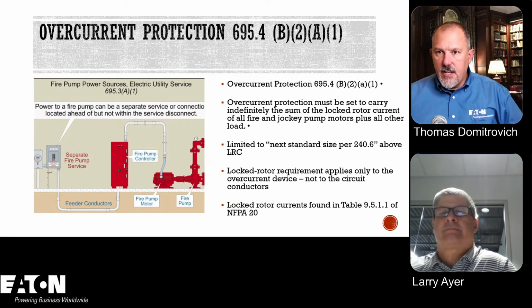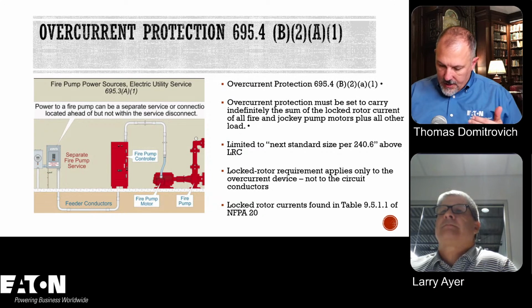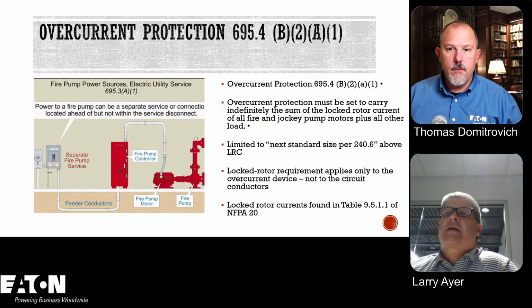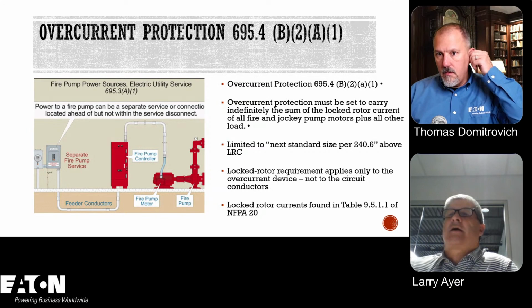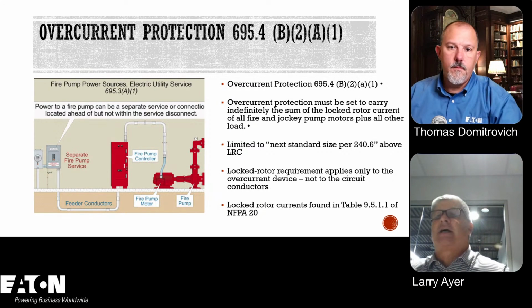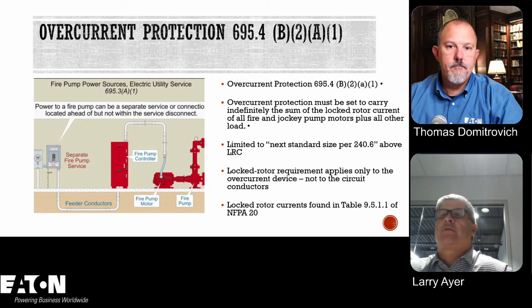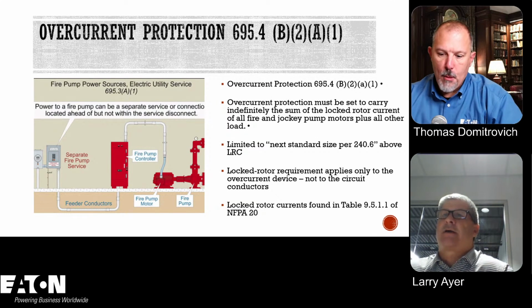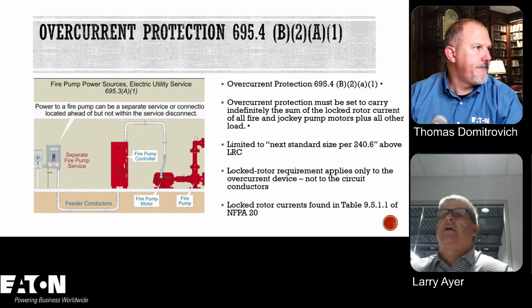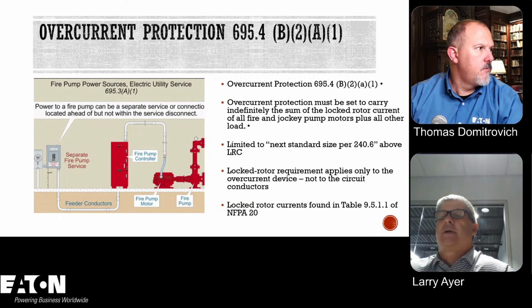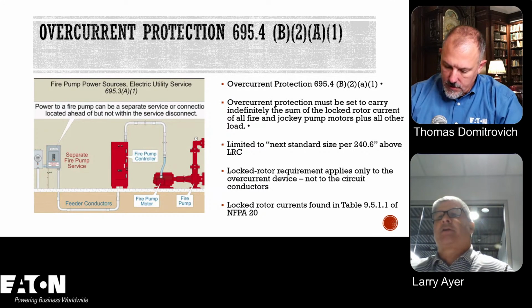And this is your 695.4(B)(2). So we're in B now. Oh yeah, (B)(2)(a)(1). And this is basically summing everything up. Yep. So if you have an overcurrent protection, it must be set to carry indefinitely the sum of the locked rotor currents plus all other fire and jockey pump motors and plus all their loads. You can still go back to 240.6 and you can go to the next standard size. And locked rotor requirements apply only to the overcurrent device, not the circuit conductor.